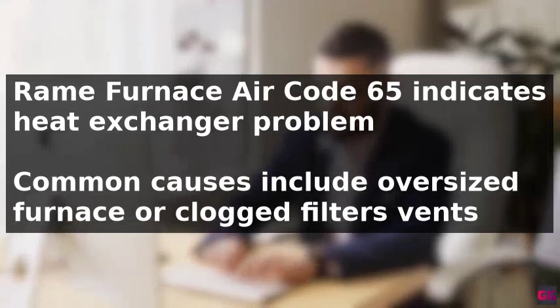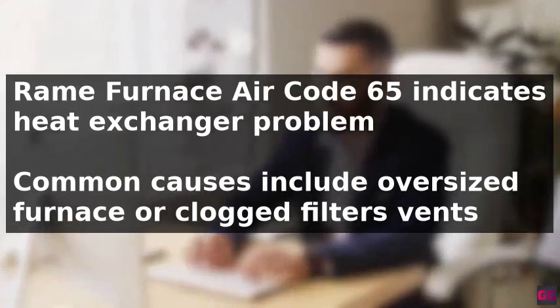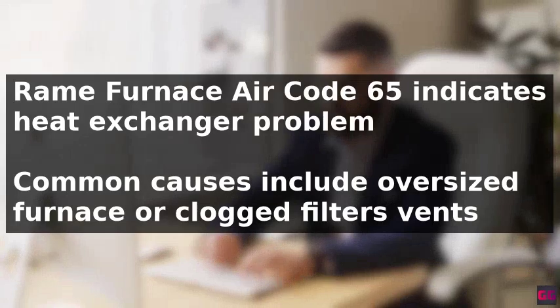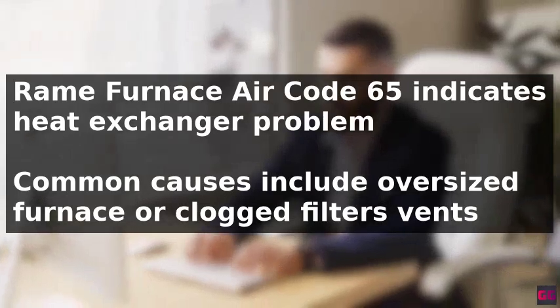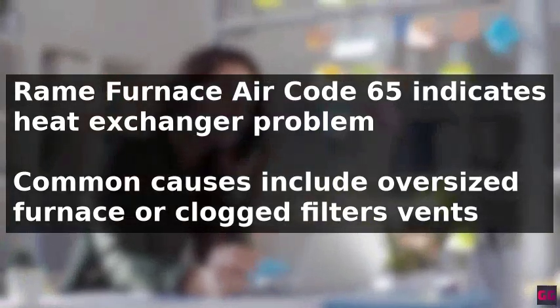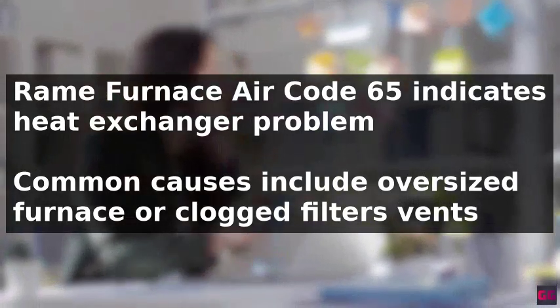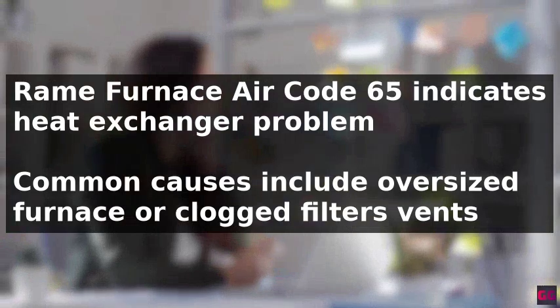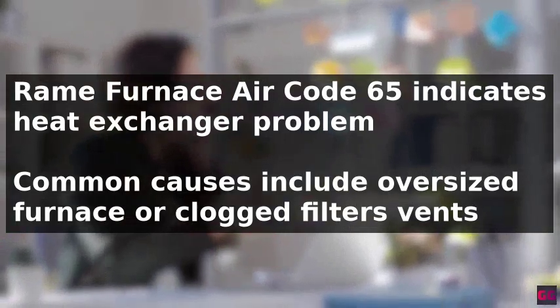To fix the Rheem furnace error code 65, it's essential to understand what this code indicates: a problem with the heat exchanger. The common causes of this issue include an oversized furnace, clogged filters, or clogged vents.